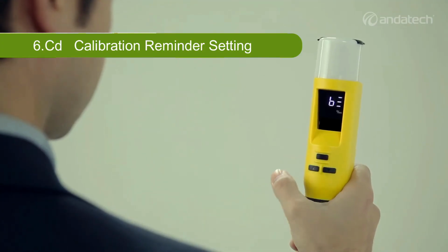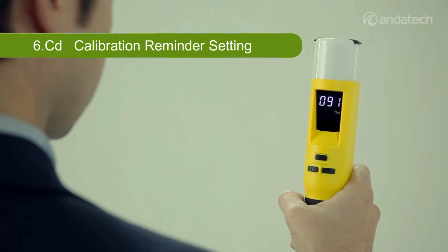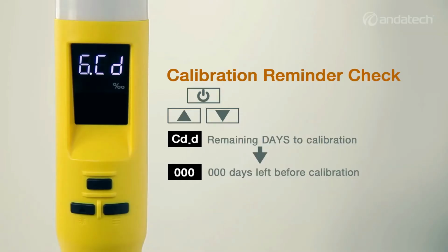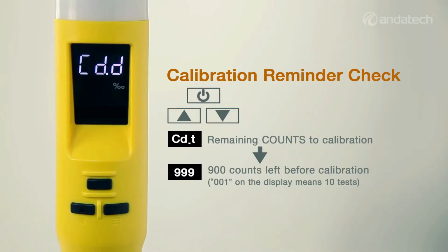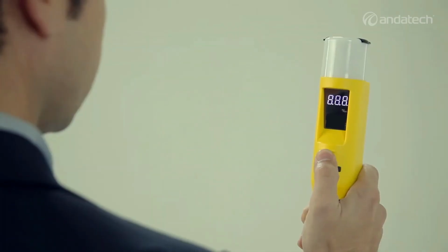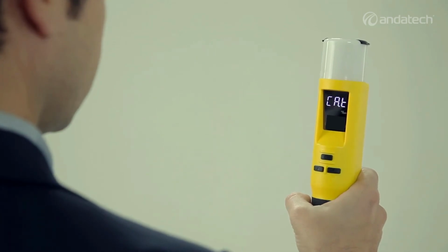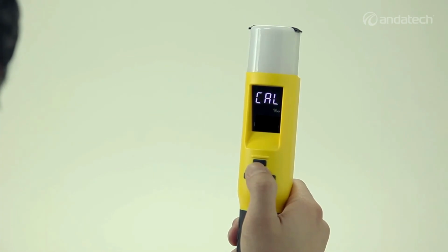Lastly, 6CD indicates the days and times remaining until calibration. CDD indicates the days that remain until calibration, from 0 to 999 days. When the set date passes, it goes into CAD, which is the grace period. After the set date of the grace period, the display will indicate CAL, and can no longer be used. CDT indicates the number of test counts remaining until calibration, from 0 to 9,990 tests. After exceeding the set test times, it will go into CAT, which is the grace period. After the set time of the grace period, the display will indicate CAL, and can no longer be used.